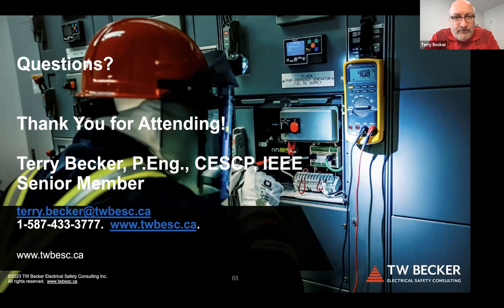I manage this topic from the standpoint of, I want the workers that need the protection to have it, but unfortunately we still have to look at financial issues. So safety is priority one. And if it's appropriate, yeah, we'll spend the money, but we've got non-electrical worker staff, we've got operators, and they don't need arc rated clothing because they're not exposed to arc flash. Now, some employers are putting everyday task wear arc rated clothing on what I'll call an operator, but they don't do and should not be exposed to arc flash.